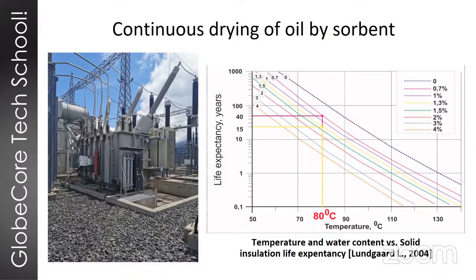So back to the graph, which demonstrates the impacts of temperature and water on transformer solid insulation. Using interpolation for these graphs shows that, for example, for a temperature of 80 Celsius, the reduction of moisture content in solid insulation from 1.3 to 0.7% actually improves the service life expectancy of such insulation by approximately 25 years, if you can believe. Okay. Next slide, please.